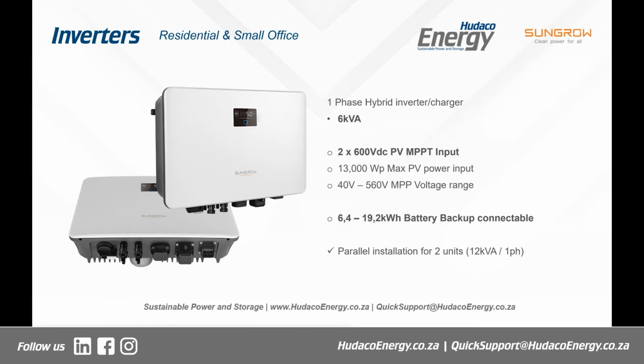Not only is your 6 kVA and your 10 kVA 3-phase hybrid that I'm about to introduce to you fast to commission, but the batteries are just as fast to commission. From unpacking the boxes to mounting them on the wall to having the system commissioned, your entire installation time is under an hour, right? That excludes your PV panels and your mounting on the roof, but the batteries, the metering, and the inverter time. Absolutely spectacular, bulletproof, saving you time on site, saving you risk on site. And I'm going to talk about the DC connection in just a moment. That should hopefully open your eyes if you're not familiar with the product yet. This is a game changer for the market. Next, please.